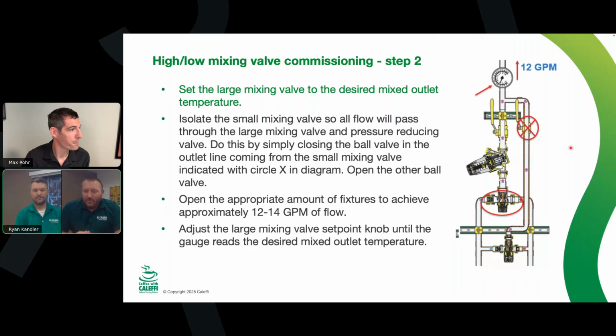For step 2, you isolate that smaller mixing valve, then go around to your fixtures and ramp up that flow to 12 to 14 GPM, then dial in the bigger mixing valve to that 120, and get that flow and make sure everything's right at that point.